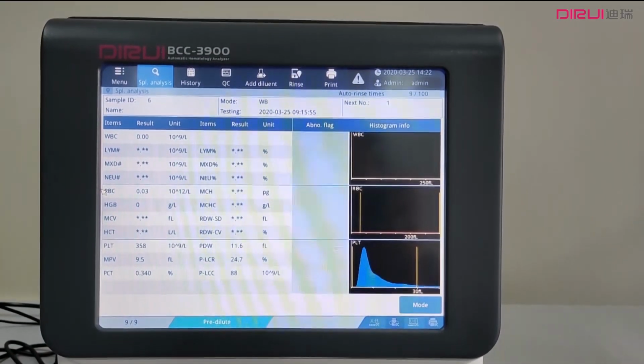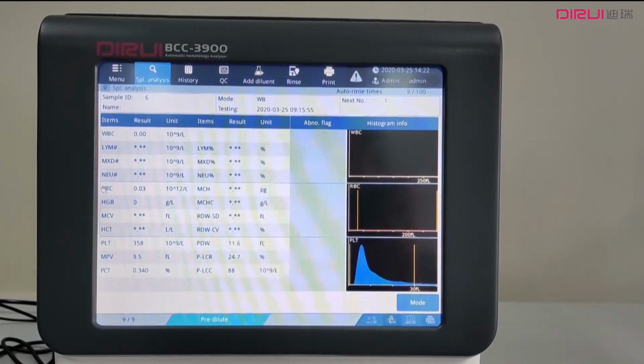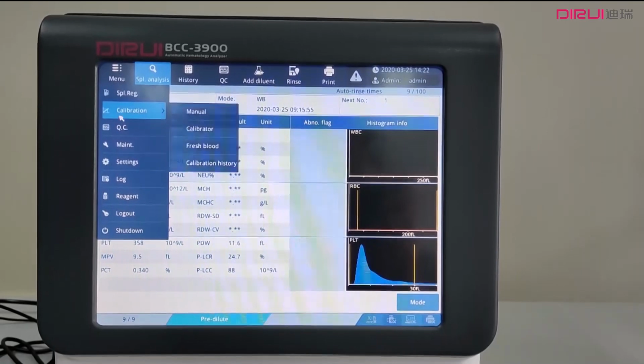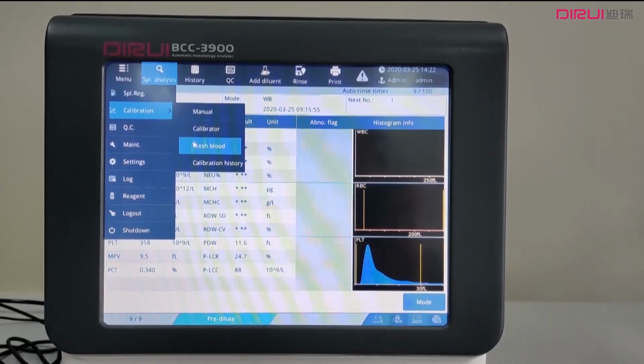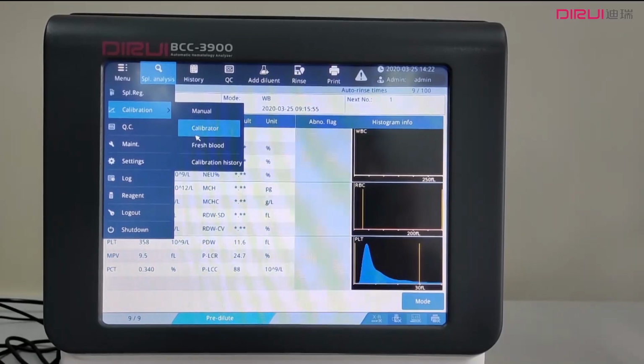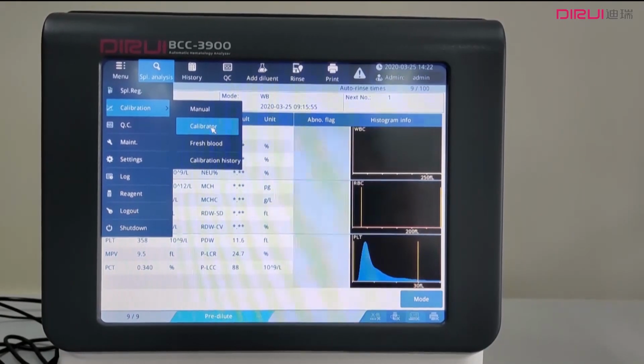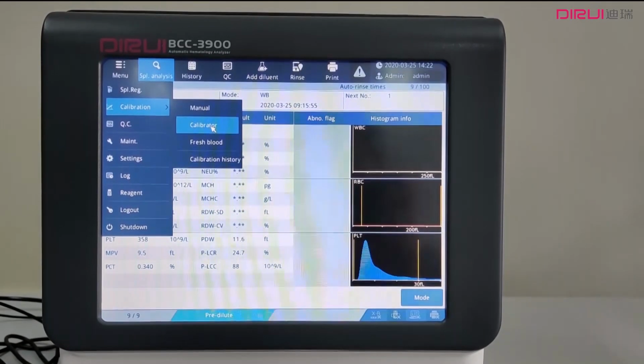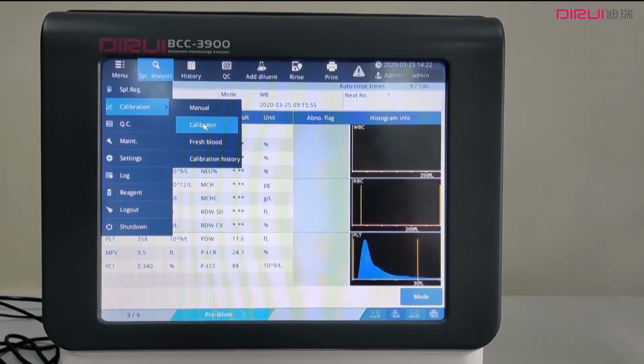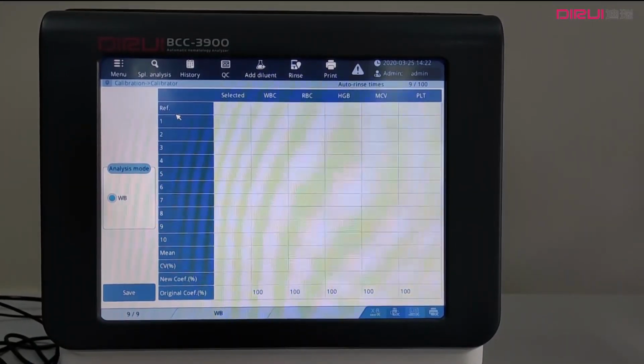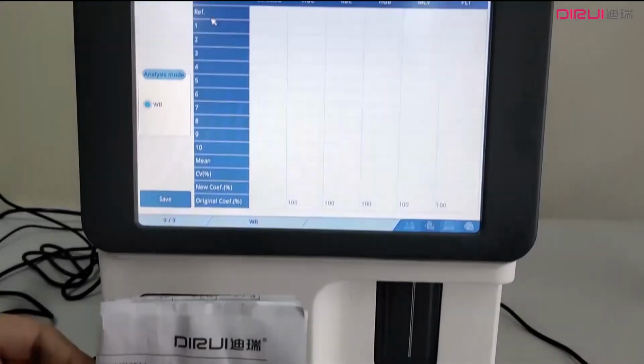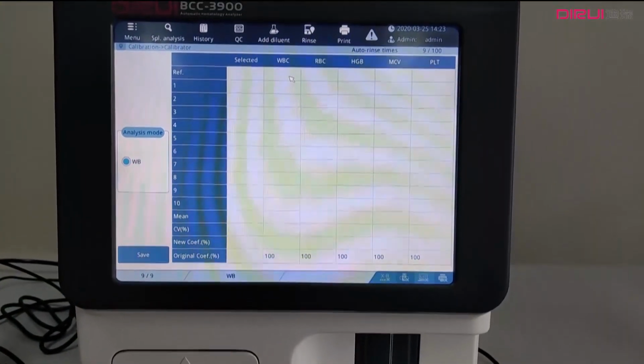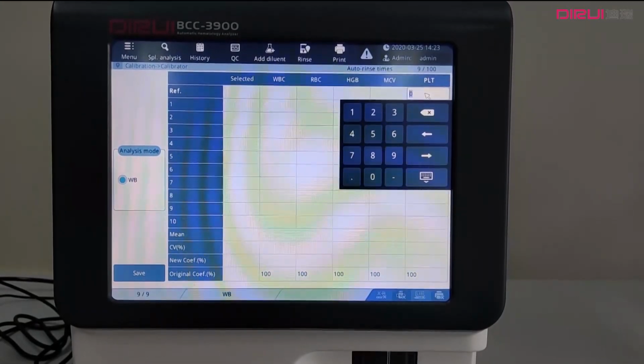After our Dirui calibrator is ready, it is time to do the calibration. For that purpose, go to menu and there is a calibration tab. Here we have three different kinds of calibrations. First we will talk about the calibrator. In this method, we will use our Dirui calibrator, and that is recommended by our company. Press calibrator and this interface will pop out. First of all, from the calibrator insert, input all of the values into this reference tab, one by one.